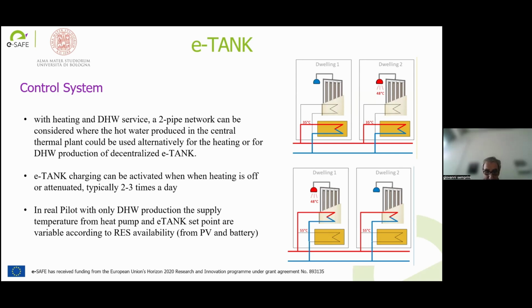This can be considered when simultaneous operation of the supply network is not always necessary, as during periods when heating is off or attenuated, and the tank charges can be activated. It is typical in many European standards that the heating system is not working continuously during the day, and when the system is off, it's possible to charge the tank.